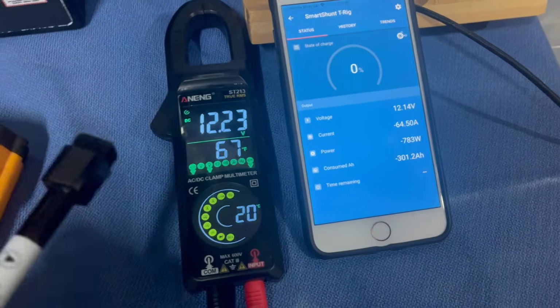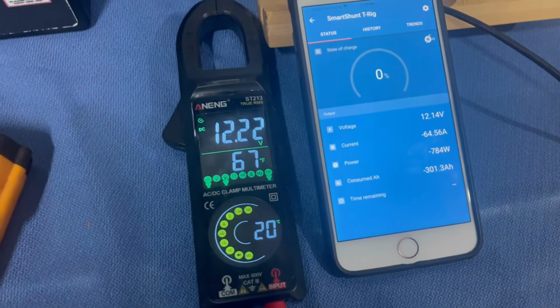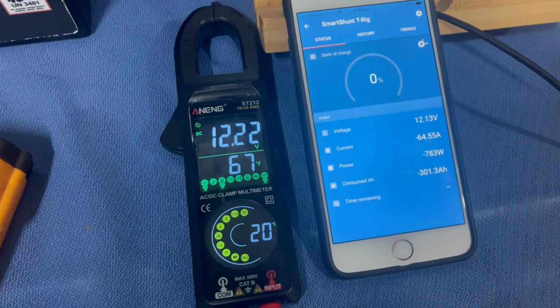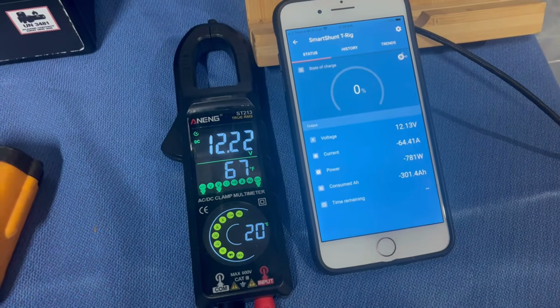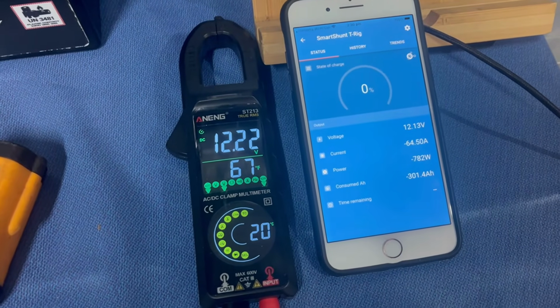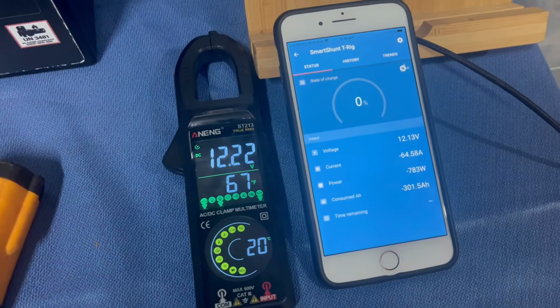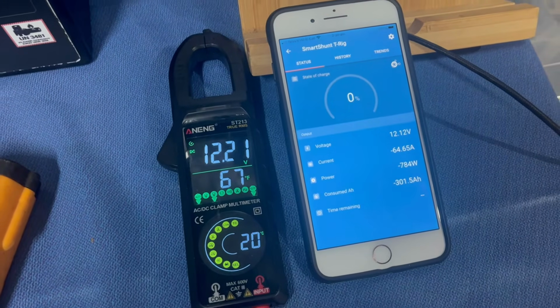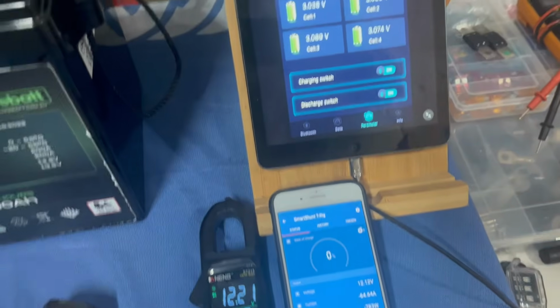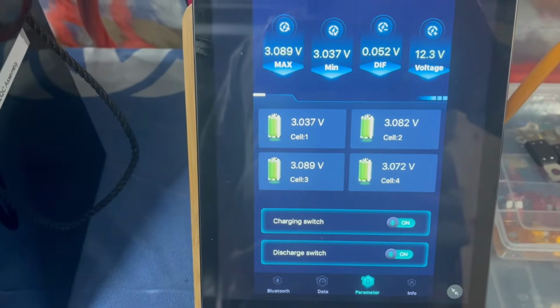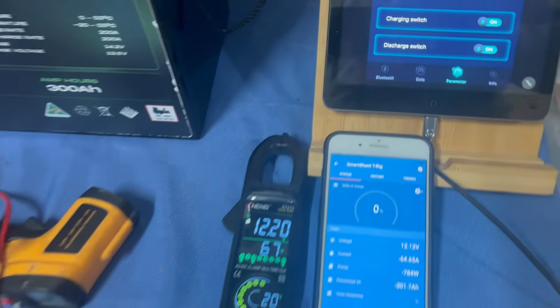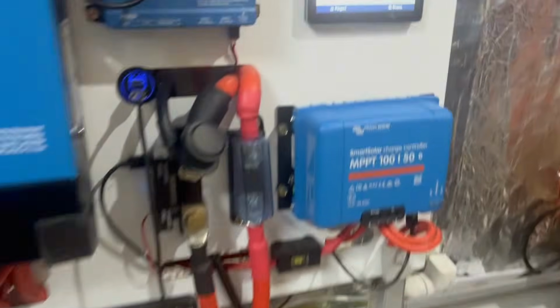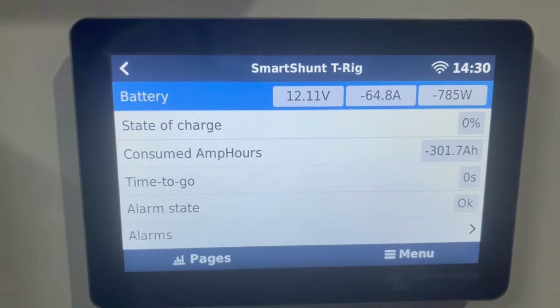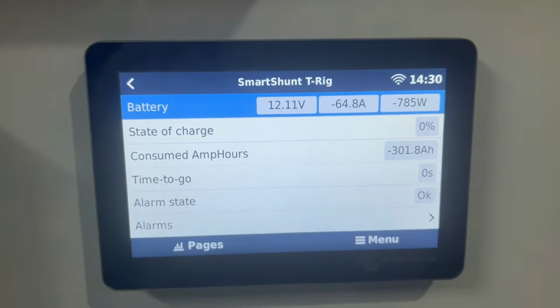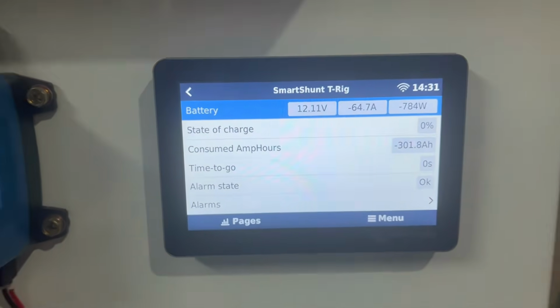So yesterday at that 12.02, I used this multimeter as the reference, so to be fair, we'll use that as a reference again today. When that hits 12 volt or 12.02 volts thereabouts, we'll check the capacity. Deviation's starting to rise now, which again is completely normal, I don't have a problem with that. You can see the load still consistent the whole way through, no issues.